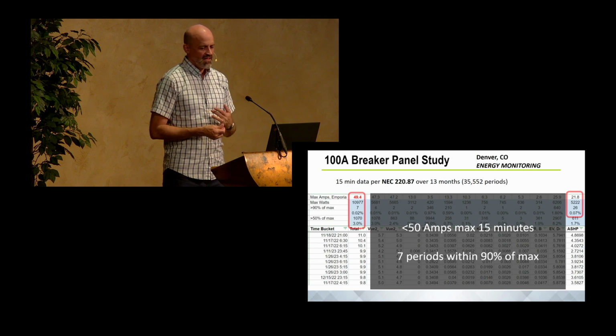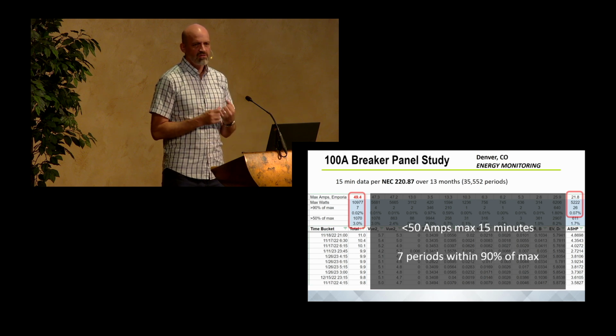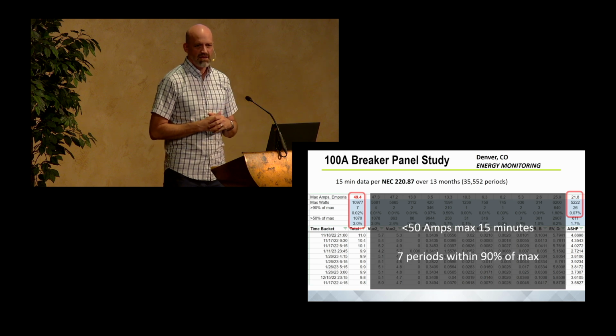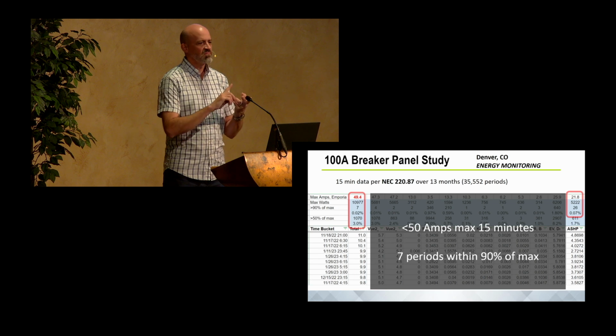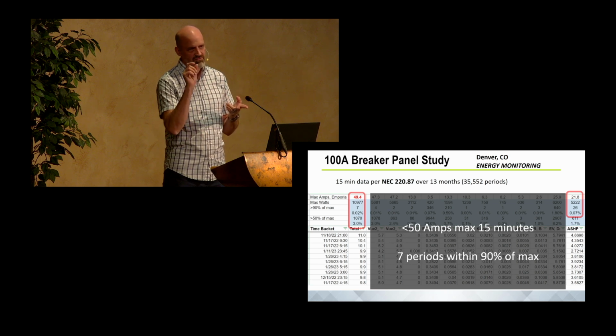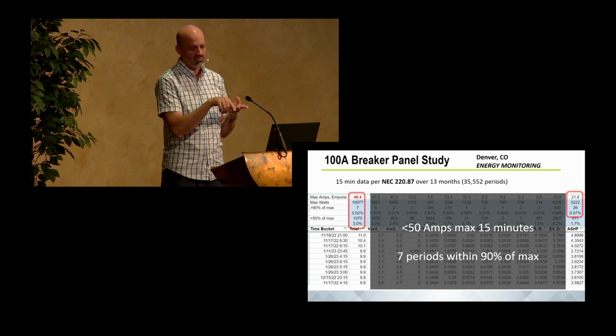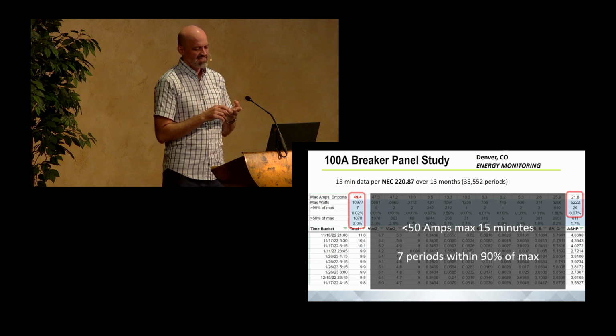After all that, the absolute worst 15 minutes was under 50 amps on a 100 amp panel, with a heat pump, all electric. To be fair, I have a water heater on gas—that's why I did all this. I wondered, can I actually add a water heater on another 30 amp circuit?